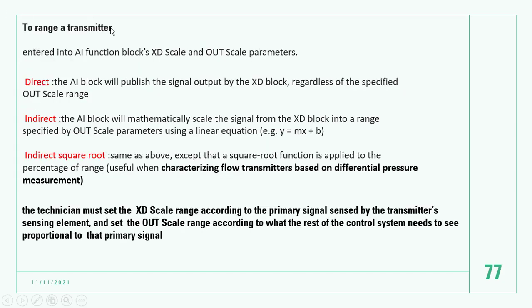If you do range transmitter, you should go to the AI function block, XD scale and out scale parameter. Okay, then here there are three kinds: direct, indirect, indirect square root. Direct means if your input senses some information, for example, level is from 0 to 2, and your output is still this, 0 to 2, it is the same thing, just a meter. You don't need mathematics, use direct. But most of the time we use indirect. With direct, the AI block will publish the signal output by the XD block.